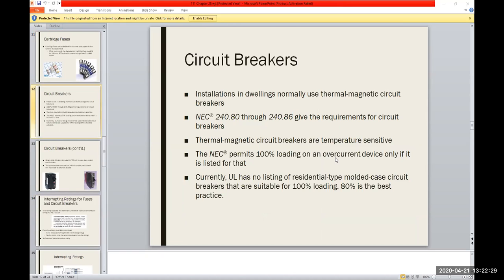And these days, most homes have circuit breakers. Like I say, it's a passive type element. It's a thermomagnetic circuit inside of the circuit breaker, fairly simple. The current has to be on for a couple of seconds to cause the circuitry to actually expand and then make the breaker trip. Otherwise, if it's just instantaneous, you'll start to get a slight swelling, but if it settles down, it'll reduce back down to size. But over a couple of seconds, it literally forces the coil to expand out, and that's what causes the breaker to trip.